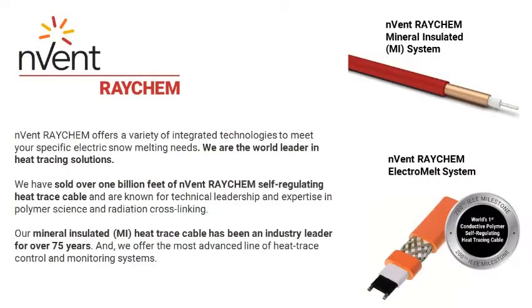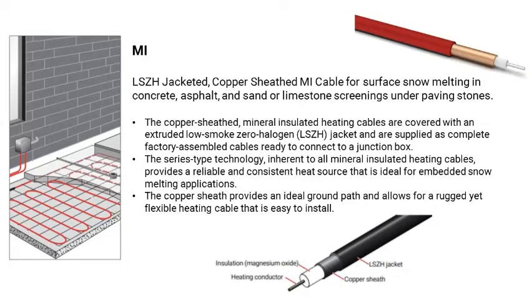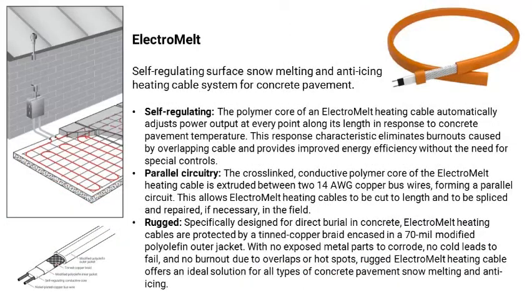nVent RAYCHEM offers a choice between two of the leading electric snow melting technologies in the industry. The first is the RAYCHEM MI system, which incorporates a heating cable that contains one or two magnesium oxide insulated metal resistors in a solid copper sheath. Because of its excellent ability to withstand high temperatures, MI is the only option to use when asphalt is the covering material. The RAYCHEM ElectroMelt system utilizes a specialized self-regulating heating cable with a conductive polymer core and nickel-plated copper bus wires protected by inner and outer polyolefin jackets.